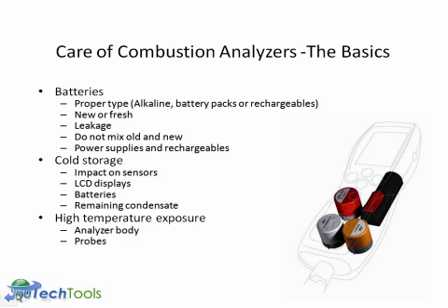Batteries, you really don't have to worry about the proper type because it comes with the rechargeable batteries. But you do want to make sure that you don't leave it on the charger all the time because you can damage the battery. And periodically, you do want to run the battery down just so it doesn't impact the battery memory. We did talk about cold storage a little bit already. It does have an impact on the sensors as far as how quickly they respond.